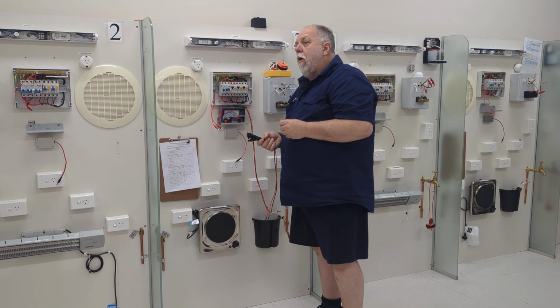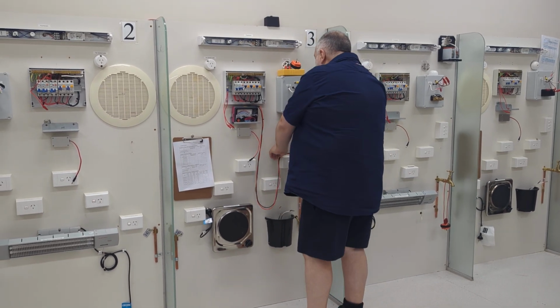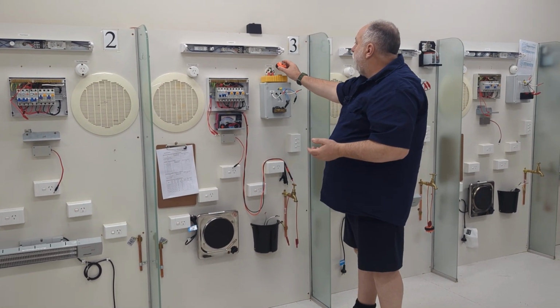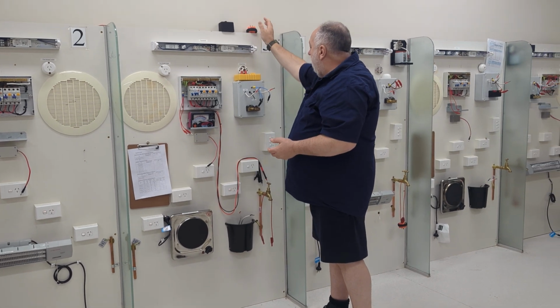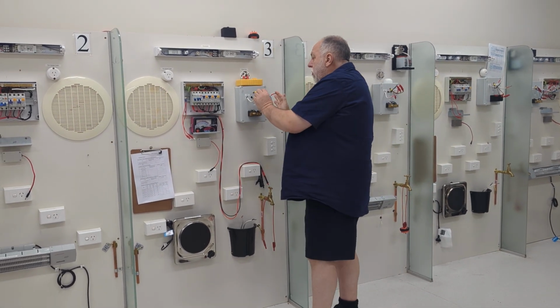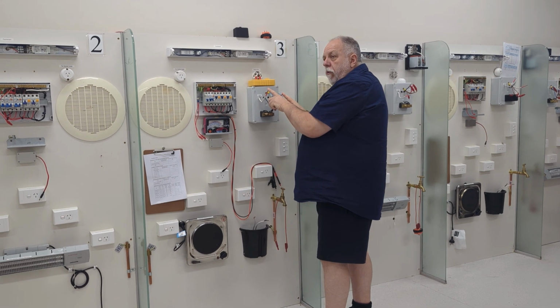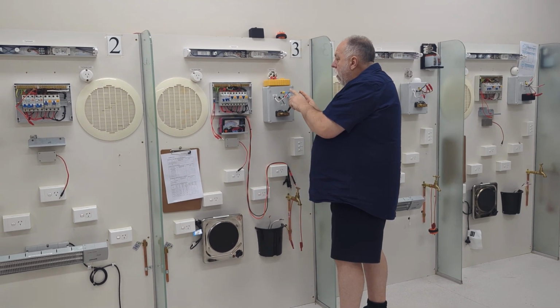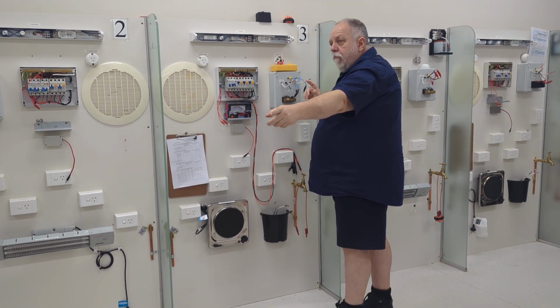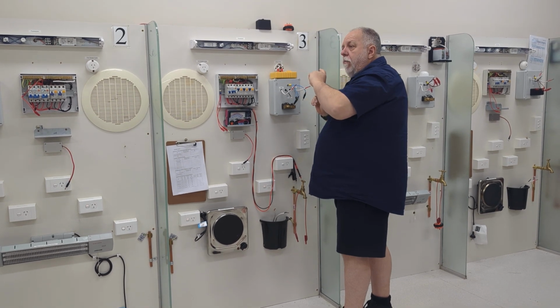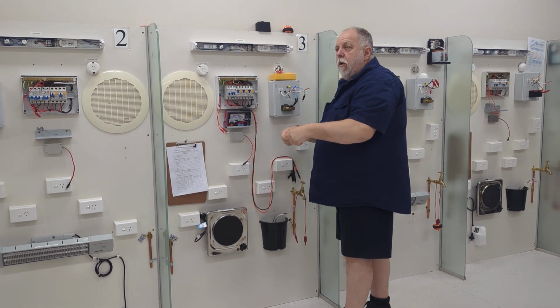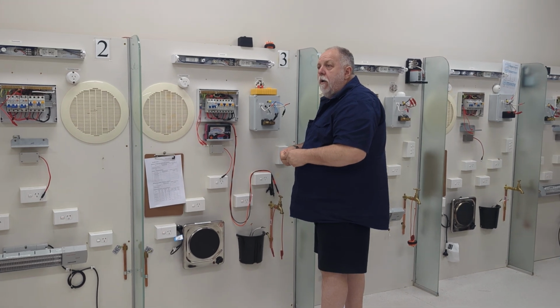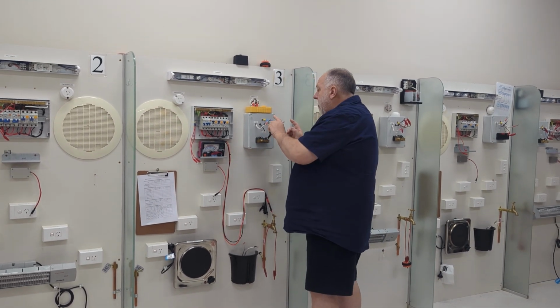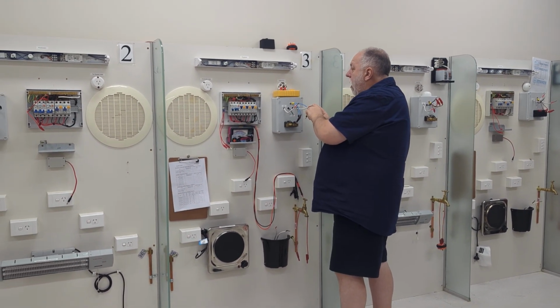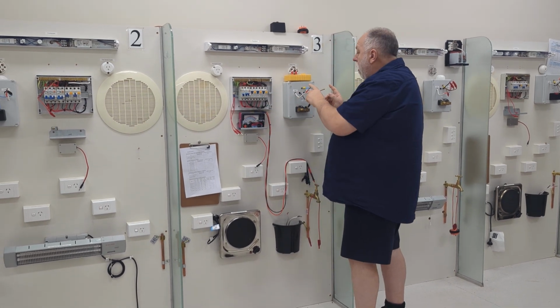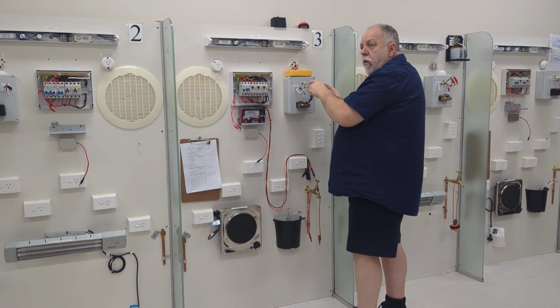Now I'm going to come back and test my whole installation. When you test the whole installation, the problem is up at the meter box, we have line and load. The line is what goes out to the pit, the underground pit. I don't want to be down in the ground trying to put clamps onto an earth pit, I've got nowhere to join to. So the other one is I've got to bring the load, which goes back from here to the main switch. I've got to join that because that's where my current gets read through. Do you understand what I'm getting at?